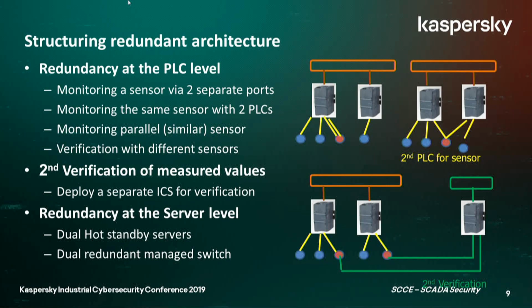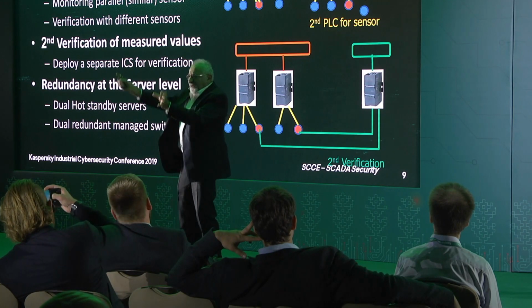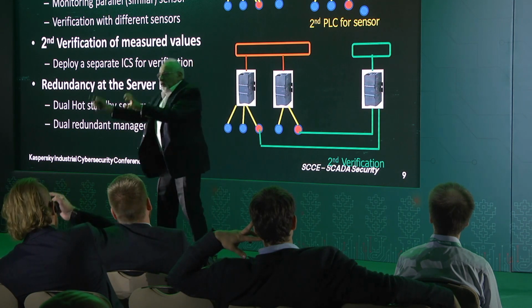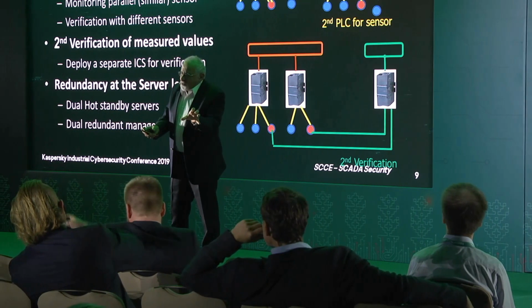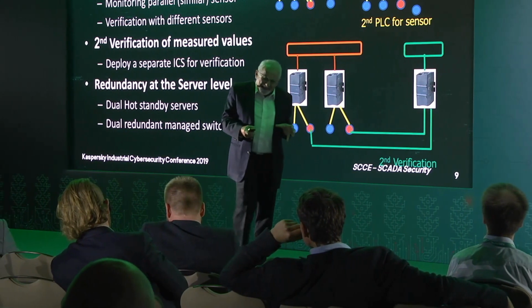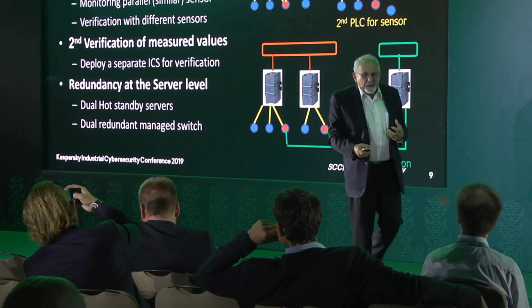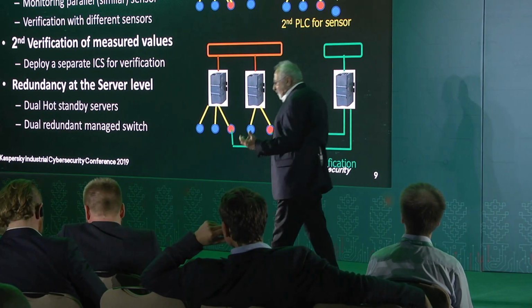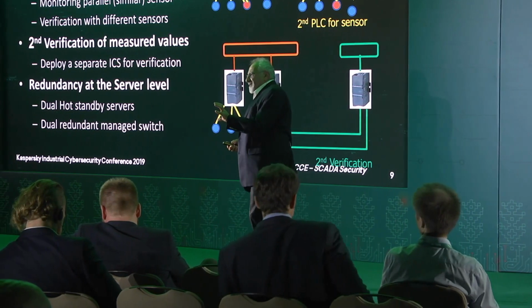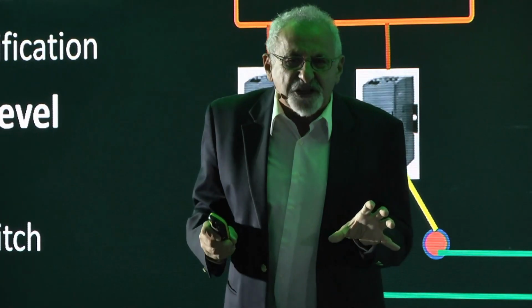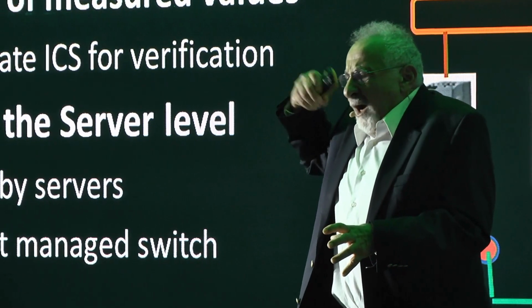We are going to strongly rely on redundancy. We all know there are more critical parts in this system and less critical parts. So for the more critical parts of the system, we will have verification. How can it be done? You can take a PLC and use two analog or digital inputs connected to the sensor. You can take two PLCs monitoring two different sensors. All the possibilities according to what makes sense, but definitely we are going to deploy redundancy in the control, and for very critical parts of the system, also redundancy in the verification. So see how this machine, how we are thinking.